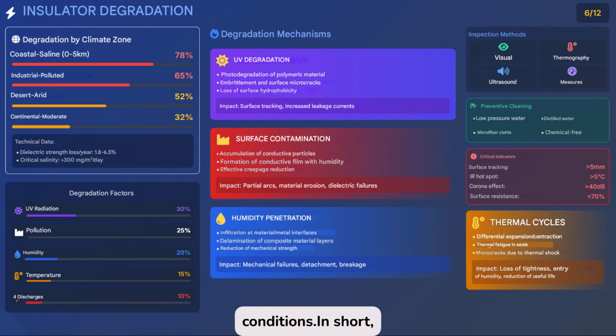In short, insulator degradation can lead to invisible failures that are not perceived by the SCADA, but have a direct impact on operations and costs. Incorporating systematic inspection into maintenance and prioritizing assets in critical areas is key to avoiding costly surprises and improving overall system reliability.